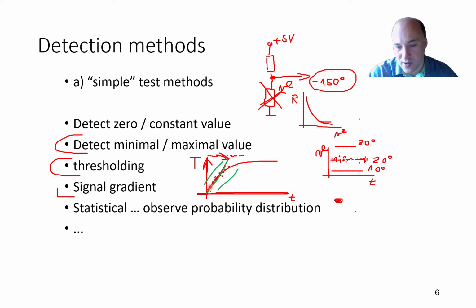And here I can really see the reading. These points here are the measured temperature, and I know that it should follow some exponential curve because I know the properties of my system. And I can calculate the gradient, in other words, how fast my signal is increasing. And this is this tangent here, shown in green.